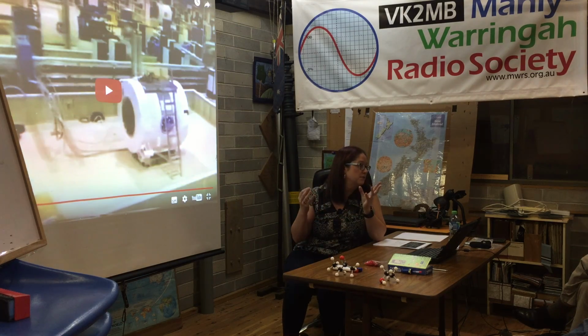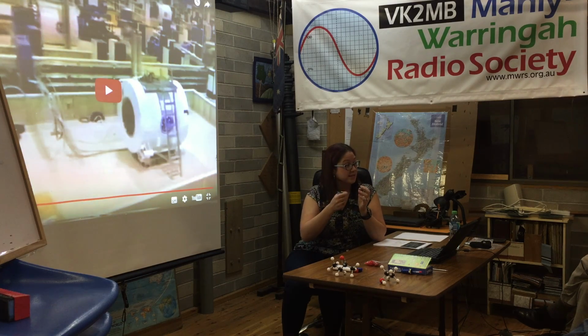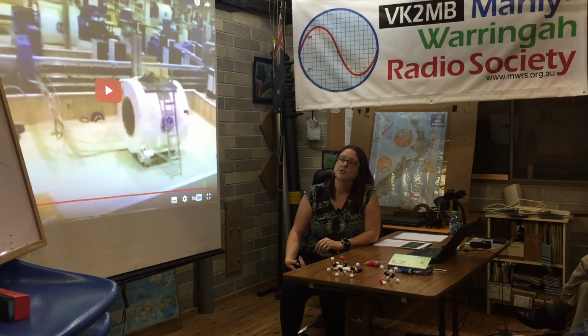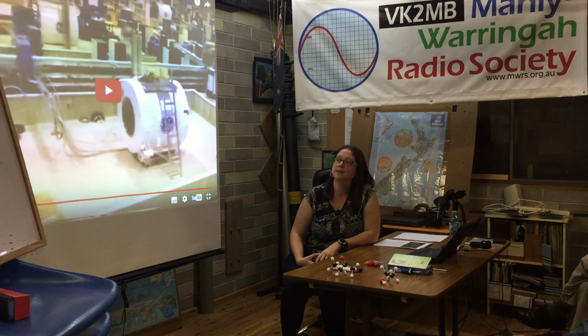It's a chain reaction. You'll see later on when I talk about magnets. There's a quench video which describes what the process of a quench actually is when that superconducting property of the windings is disrupted, and you get a chain reaction of heating, resistive heating throughout the windings, and then the cryogens boil off very violently and are ejected from the magnet, and that happens quite quickly, and then the field dissipates, and it's just a big can of metal at that point.